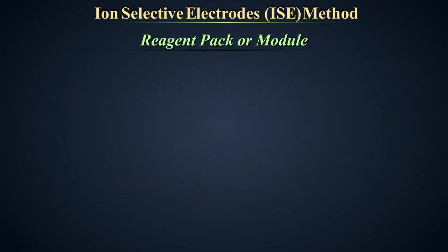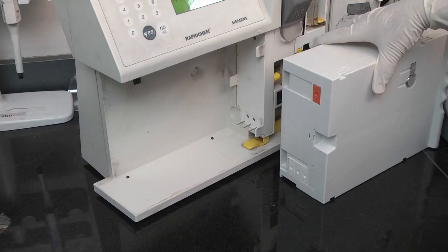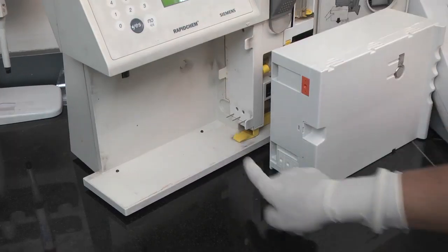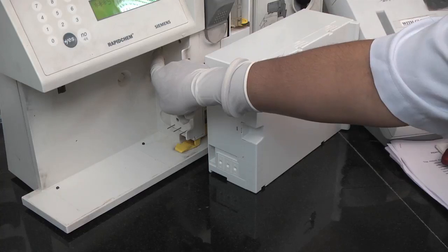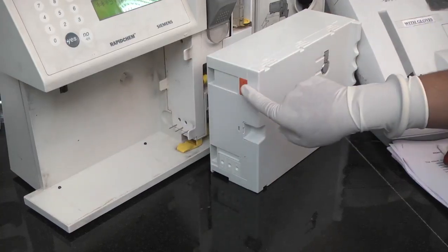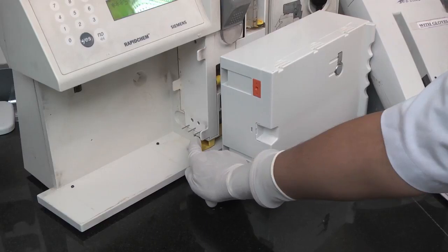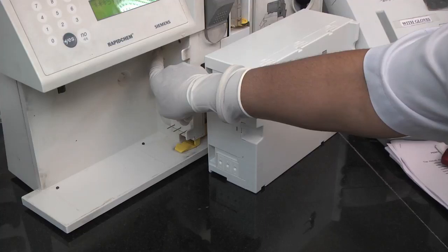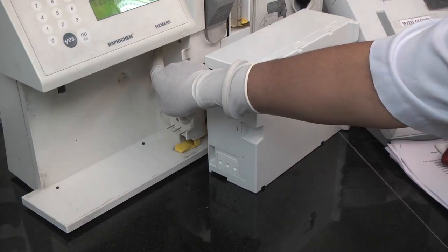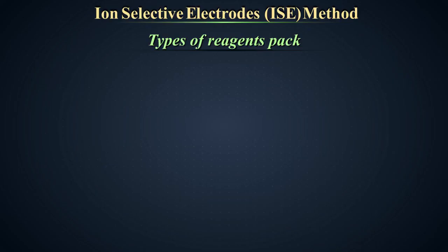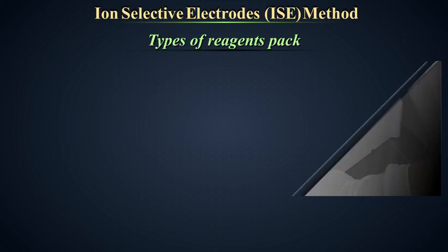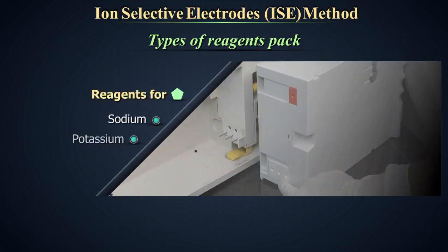Reagent pack or module. The reagent pack is a rectangular box which stores the reagents in the lower half and the waste is generated in the upper half. The left side of the pack has three inlets for the reagent tubes on the main body of the analyzer and also one inlet for the waste generated. Two types of reagent packs are commonly available: one with reagents for sodium, potassium, and chloride, and the other with reagents for sodium, potassium, and lithium.